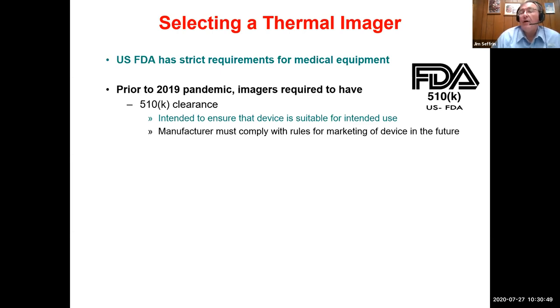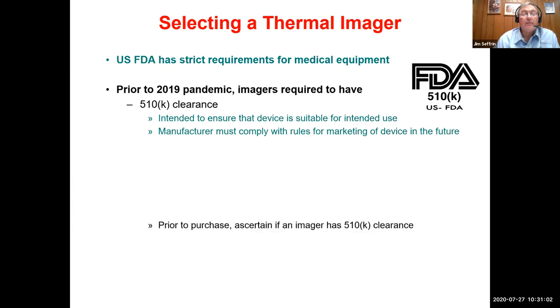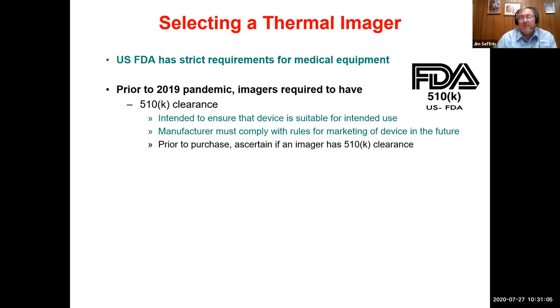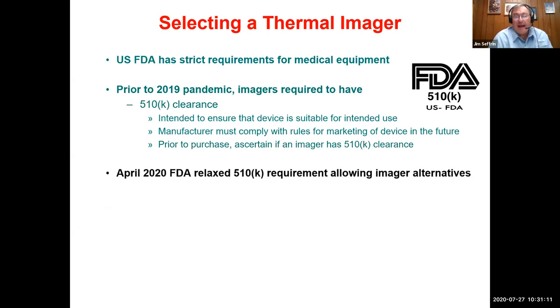For those of you that own FLIR systems, thermal imaging systems, you may find, if you check with FLIR, that the instrument you currently have may likely have a 510K clearance already. So prior to purchasing a system, ascertain if the imager has a 510K clearance. Now, in April 2020, just a few months ago, the FDA relaxed this 510K requirement, allowing for imager alternatives. So prior to April, you had to have a 510K clearance. At present, that has been waived. If you have a 510K clearance for your equipment, you can still use it. But if you don't have one presently, it's not a deal breaker for using your instrument for elevated body temperature screening.